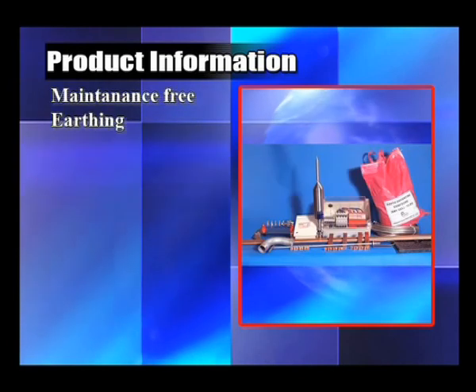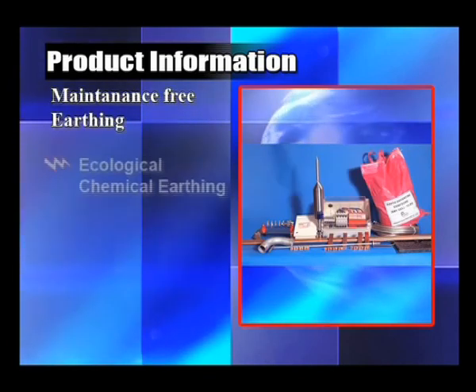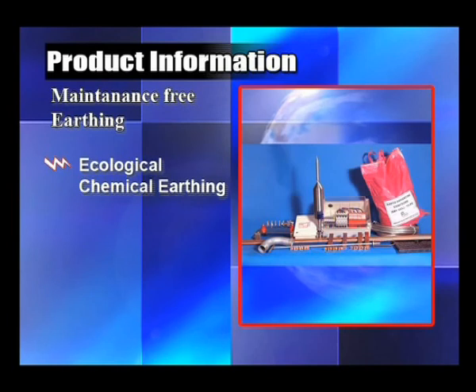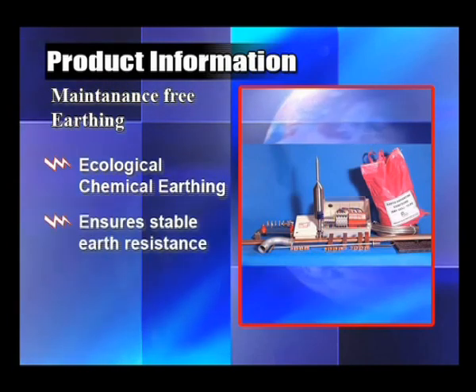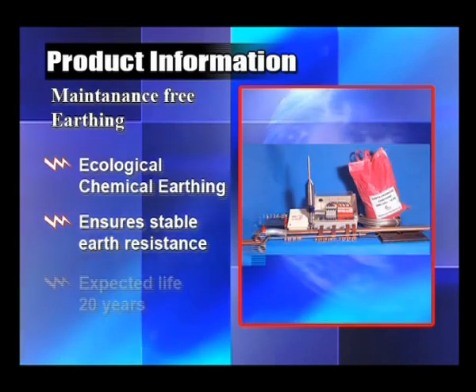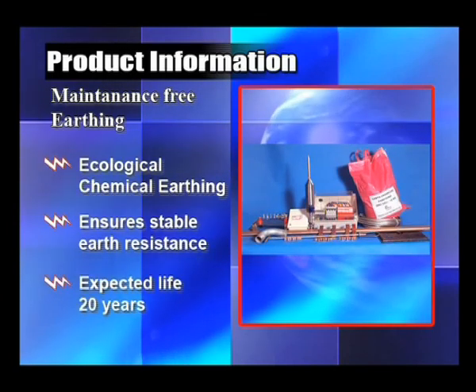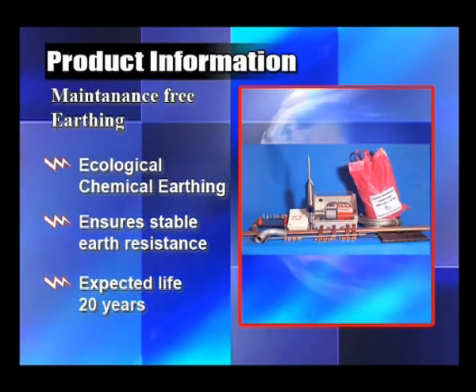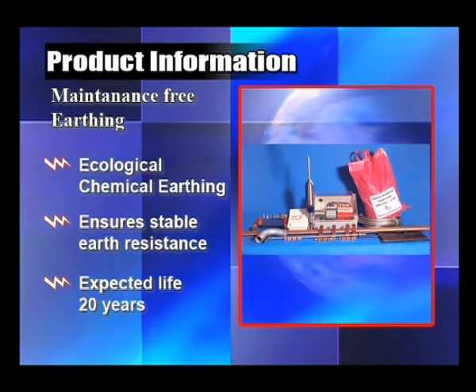Maintenance-free earthing. This is an ecological chemical earthing. It ensures stable earth resistance of less than 2 ohms depending on soil condition. Expected life of chemical earthing is 20 years, even under temperature variation of minus 40 to plus 60 degrees centigrade.